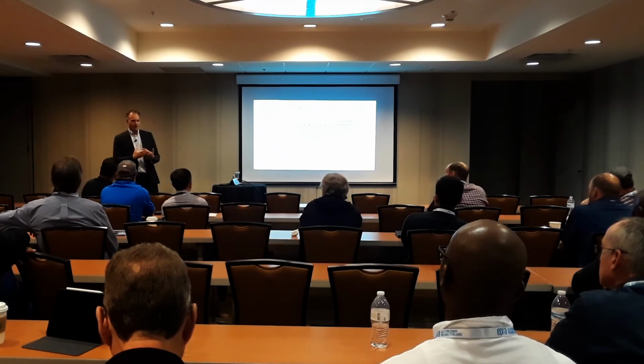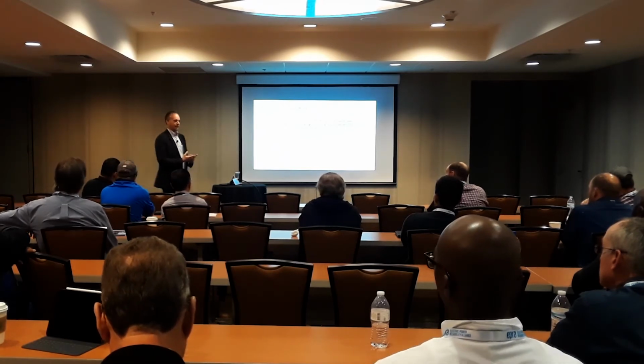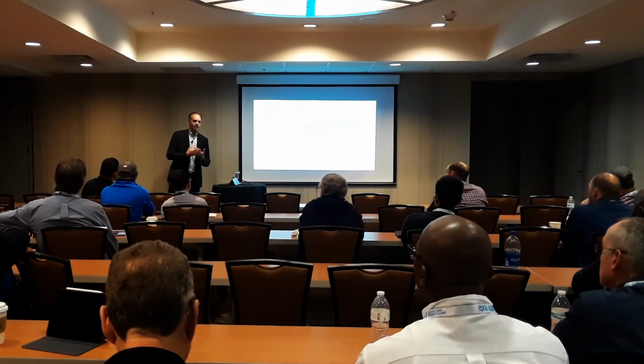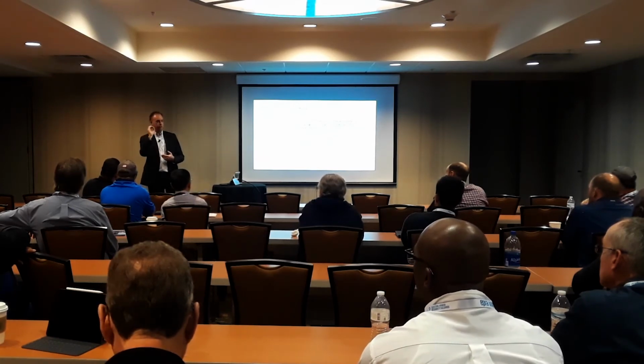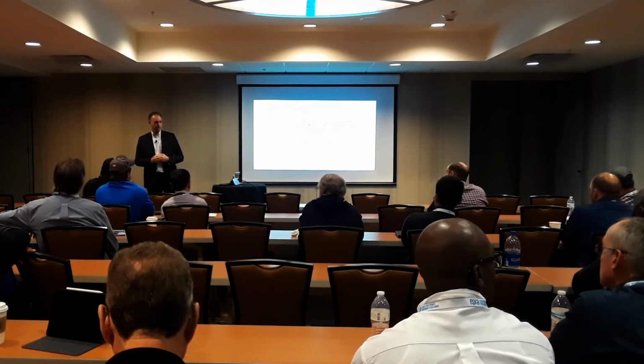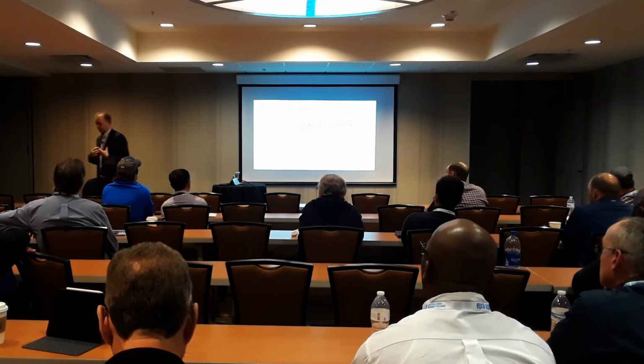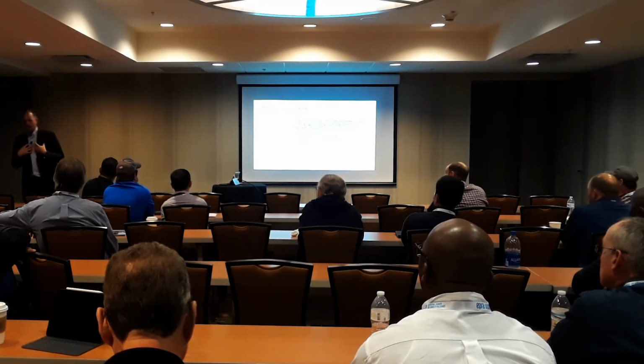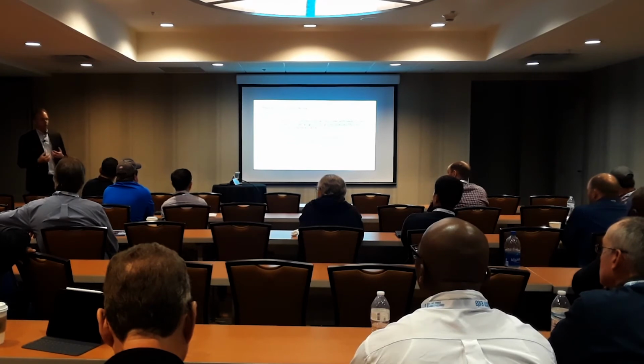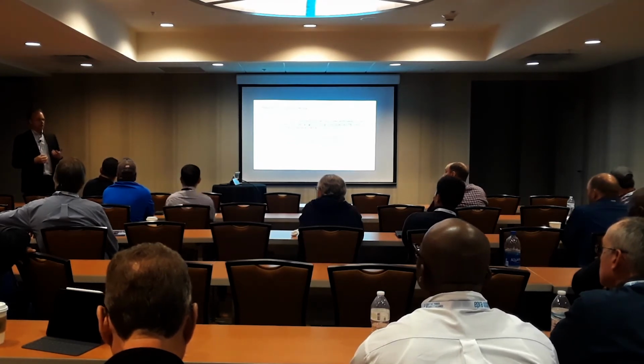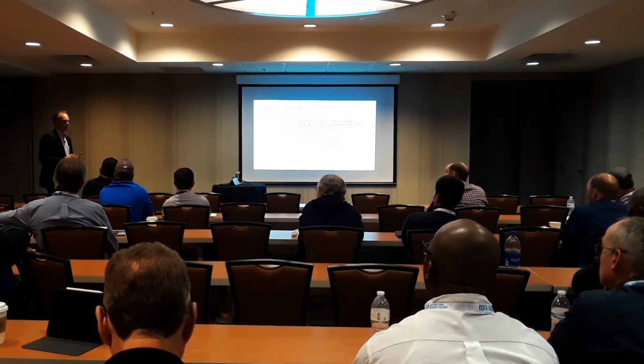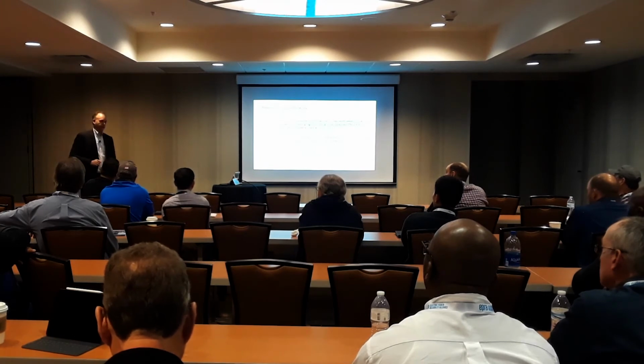In their O&M manuals, they will write things like, go and tighten it every 12 months. It is based on absolutely this much science. Zero, none, right? In fact, the guy that writes the manual, in that case me or one of my staff, would probably say, well, let's make a recommendation. We need them to tighten it every once in a while. They should do it every 24 months. And we would write that into the manual.